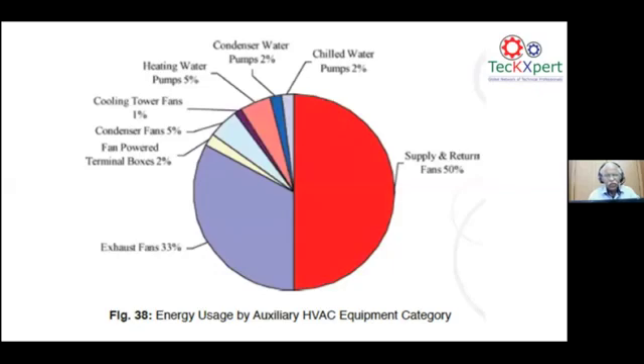This is on the chiller side, on the air conditioning side. On the compressors and the auxiliaries, you find the auxiliaries consuming 50% on the supply and return fans only. The exhaust fans are around 30%. For all the other pumps, the consumption is less.